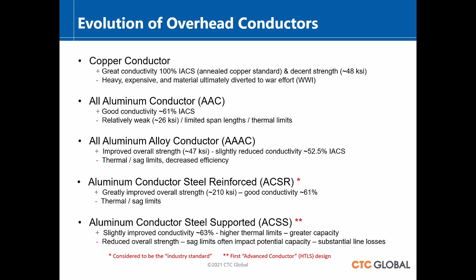About 1970, they came up with the first of what we'd call advanced conductors, or low sag conductors. The ACSS, a steel-supported structure, let them get more aluminum on there if they wanted a trapezoid type wire like we do. It was a bit stronger, and the alloys let them run hotter. That brought us to advanced conductors, constantly looking at how to get stronger strength while maintaining good efficiency.